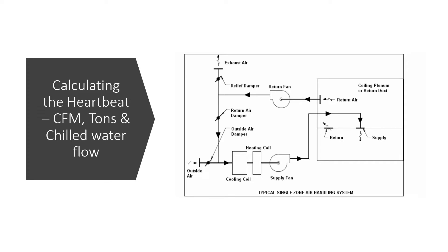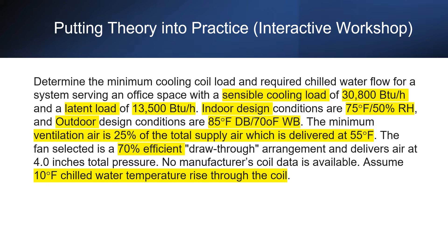Let's get to the heart of the matter: understanding the airflow and cooling needs of our project. We will assume that we already know the cooling load — the amount of heat we need to remove. This can be calculated through manual equations or by using specialized software tools. Consider the following example: determine the minimum cooling coil load and required chilled water flow for a system serving an office space with a sensible cooling load of 30,800 BTU per hour and a latent load of 13,500 BTU per hour.